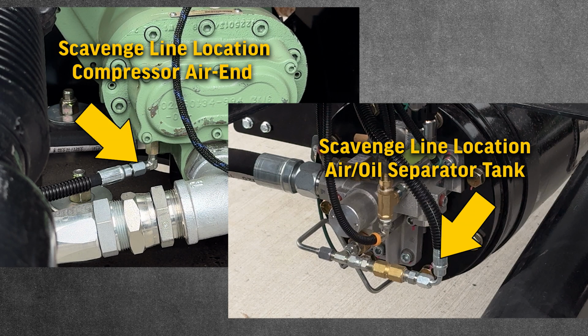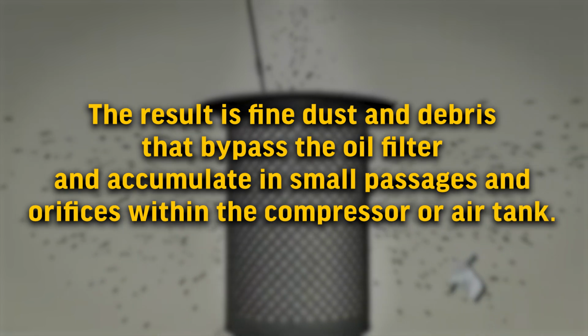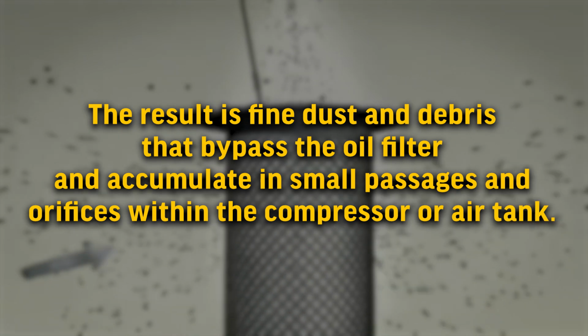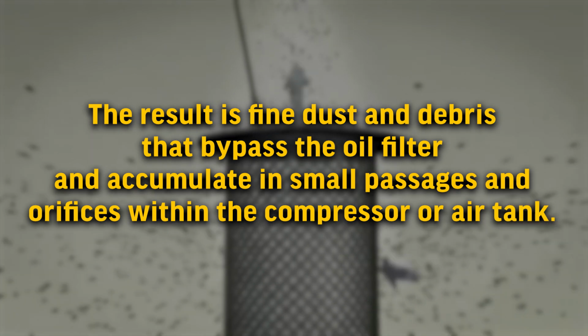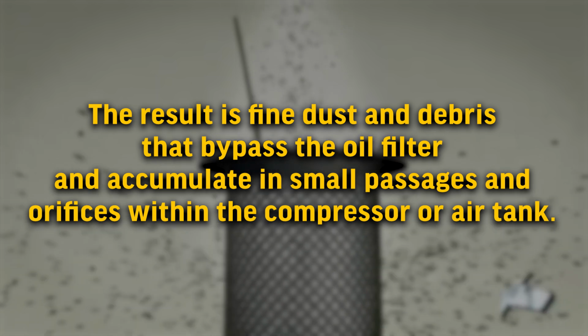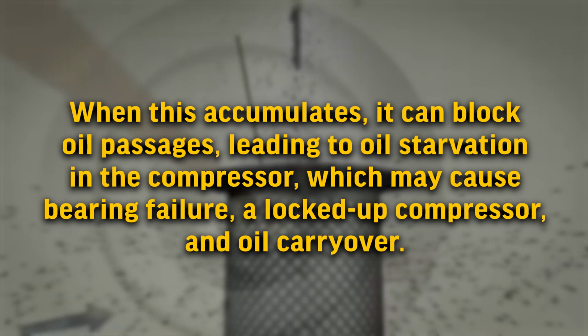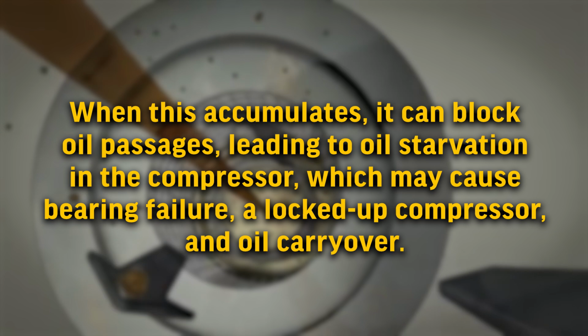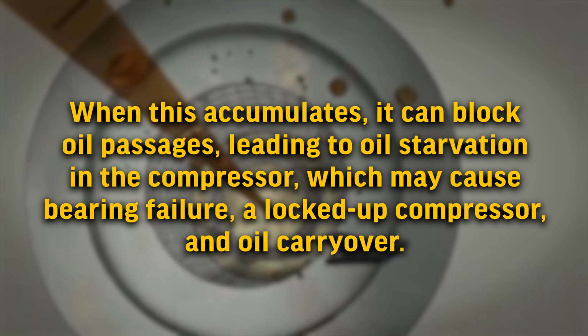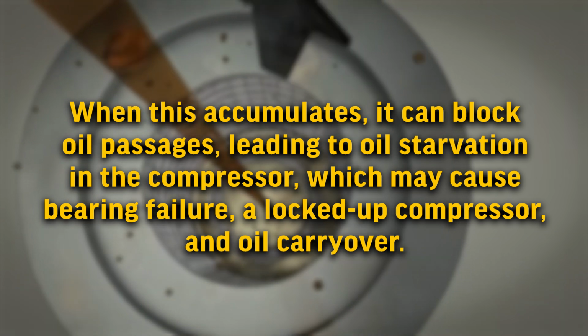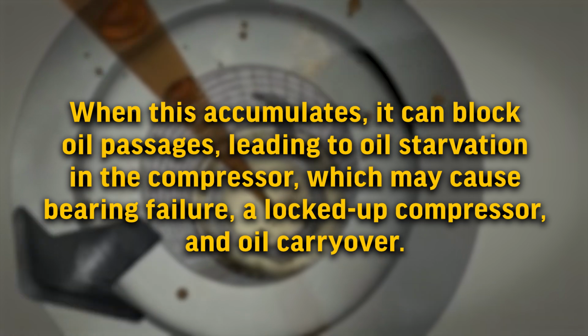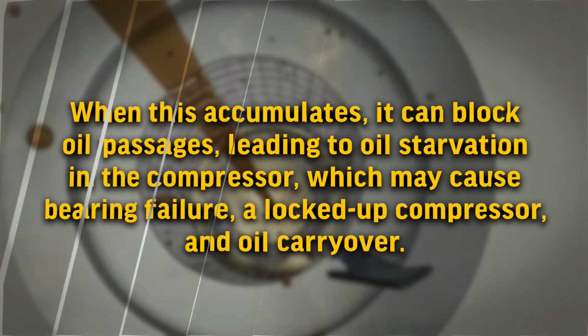One main cause is that the oil scavenge line gets clogged. The result is fine dust and debris that bypass the oil filter and accumulate in small passages and orifices within the compressor or air tank. When this accumulates, it can block oil passages, leading to oil starvation in the compressor, which may cause bearing failure, a locked-up compressor, and oil carryover.